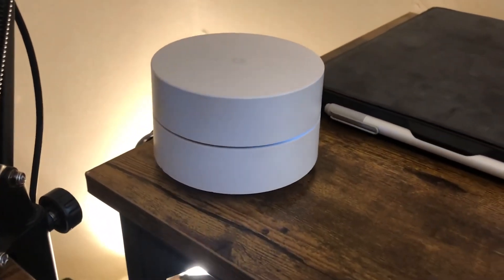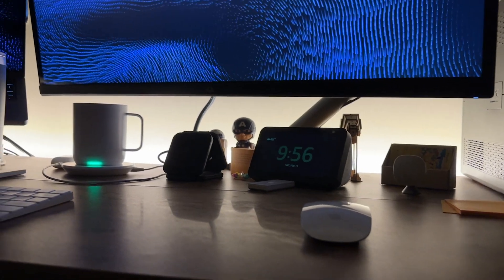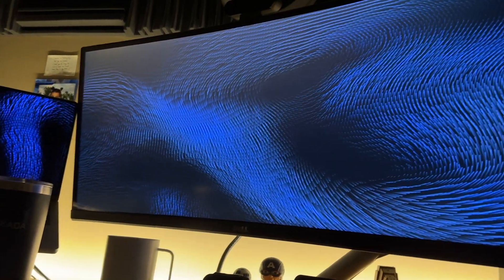As I was researching and prioritizing these devices, the internet-specific devices — the fiber ONT, the fiber modem, the AT&T Google Wi-Fi access point — really only draw between 14 and 16 watts at any given time, which on the 1000 UPS only draws about 2% capacity. So very low-powered devices, meaning I'd like those to stay online for as long as possible, especially with all the battery-powered electronics I have. For things like my laptop docking station, monitor, and home lab, I'd like them to last at least about half an hour.